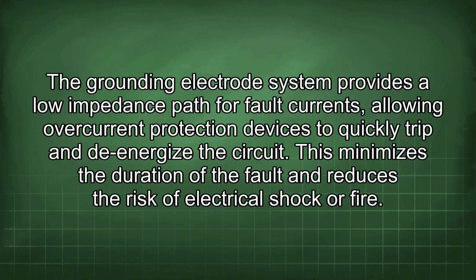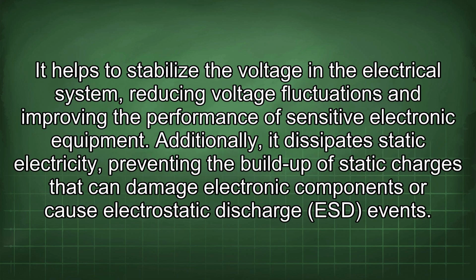The grounding electrode system provides a low impedance path for fault currents, allowing overcurrent protection devices to quickly trip and de-energize the circuit. This minimizes the duration of the fault and reduces the risk of electrical shock or fire. It helps to stabilize the voltage in the electrical system, reducing voltage fluctuations and improving the performance of sensitive electronic equipment. Additionally, it dissipates static electricity, preventing the buildup of static charges that can damage electronic components or cause electrostatic discharge (ESD) events.